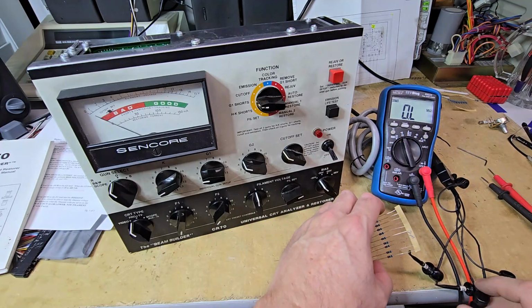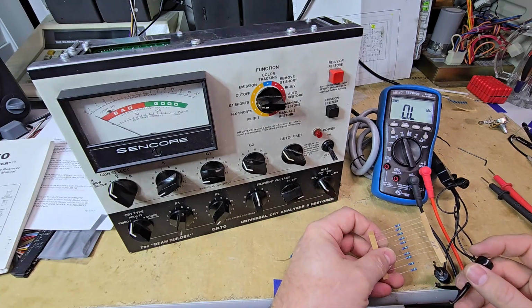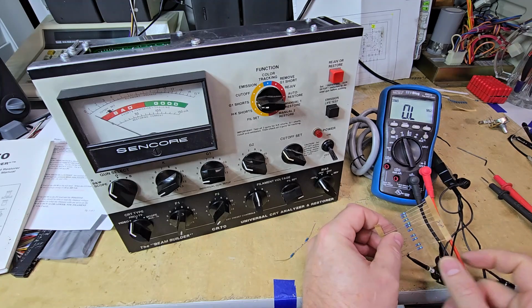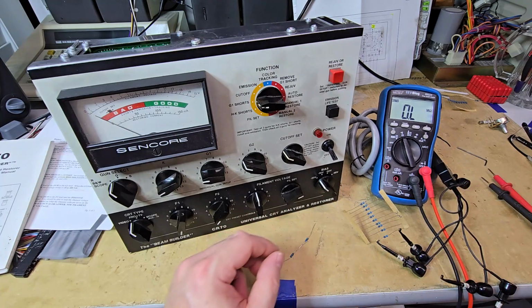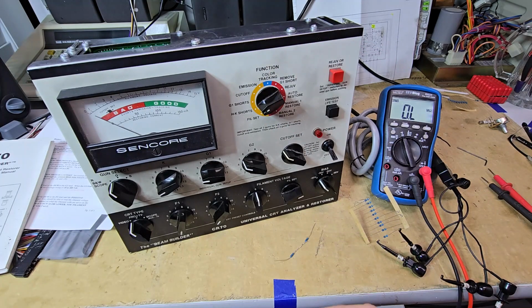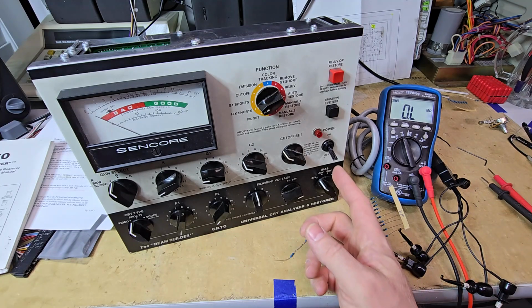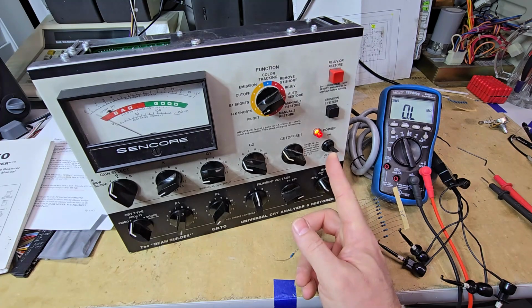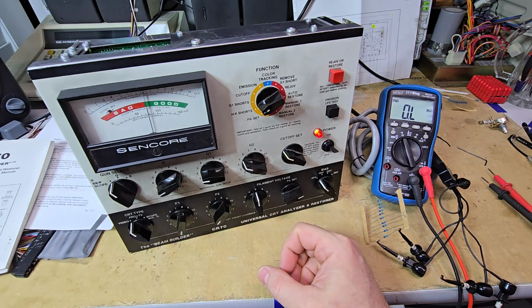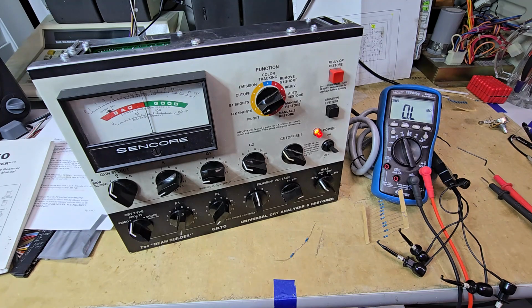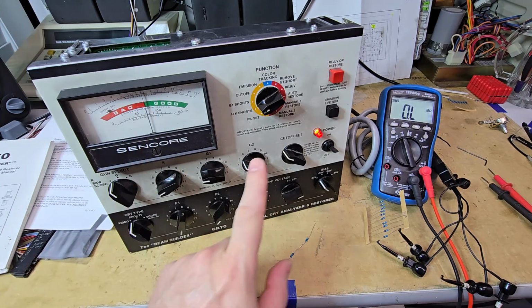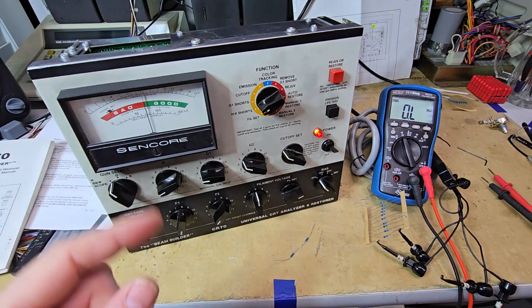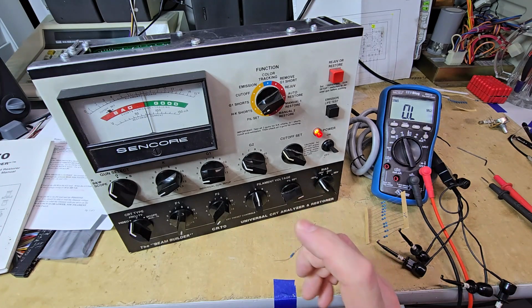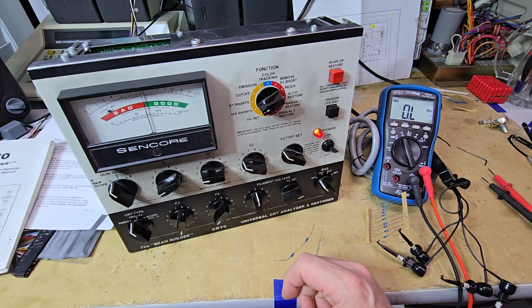And now we're going to filament voltage 2. Heater to cathode. All right, change that to heater to cathode. 2 mega ohms, F and K. F2 and K is what I'm doing. Yeah, see, I actually already adjusted this, and so it's right on the 2 mega ohm on the HK short. It's right at the center line. It's a little bit difficult to have it in both cases be perfect, but it is straight up for HK short. It's good.